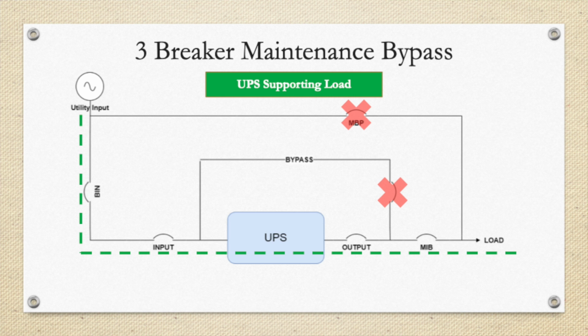This next drawing is a 3-breaker maintenance bypass, which is generally used when the customer only has 1 feeder breaker to the UPS system available. The 3 breakers that make up the bypass are BIN, which is the bypass or utility input to the UPS, MIB, which is the output isolation breaker, and MBP, which is the maintenance bypass breaker. On this drawing, we're showing the UPS online supporting the load. So BIN is closed, MIB is closed, and MBP is open.